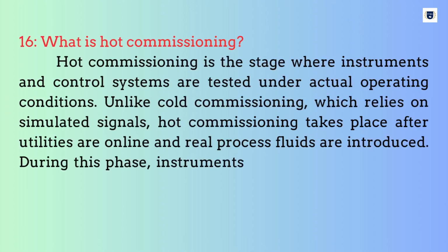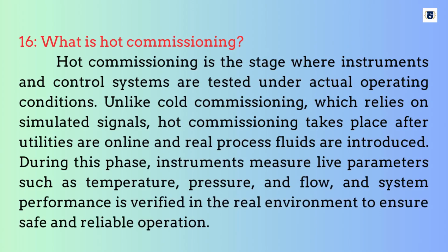What is hot commissioning? Hot commissioning is the stage where instruments and control systems are tested under actual operating conditions. Unlike cold commissioning, which relies on simulated signals, hot commissioning takes place after utilities are online and real process fluids are introduced. During this phase, instruments measure live parameters such as temperature, pressure, and flow, and system performance is verified in the real environment to ensure safe and reliable operation.